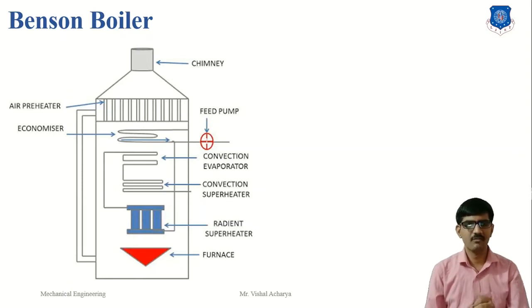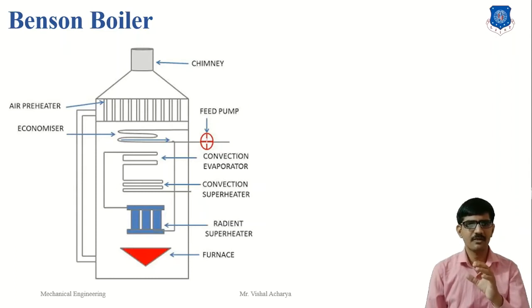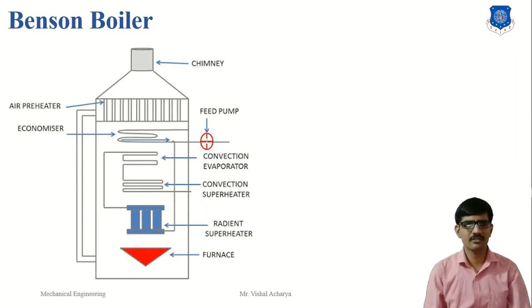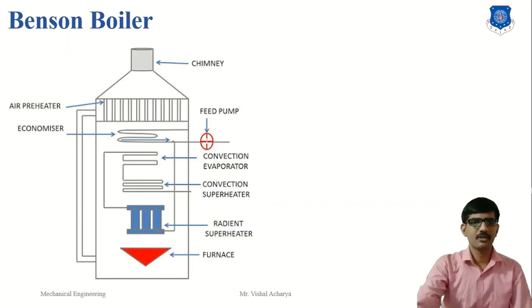The construction parts of the Benson boiler include: an air pre-heater, which preheats the air before entering the furnace and increases burning efficiency; an economizer, which heats the water to a certain temperature; a radiant superheater, which heats the water using radiation from the burnt fuel and raises it to supercritical temperature; a convection evaporator, which superheats water and converts it into steam using the convective mode of heat transfer. The convective superheater superheats the steam to the desired temperature of nearly 650°C. The furnace is where fuel is burned, and the feed pump supplies water at supercritical pressure of 225 bar.